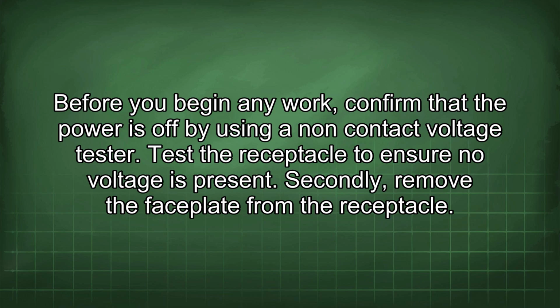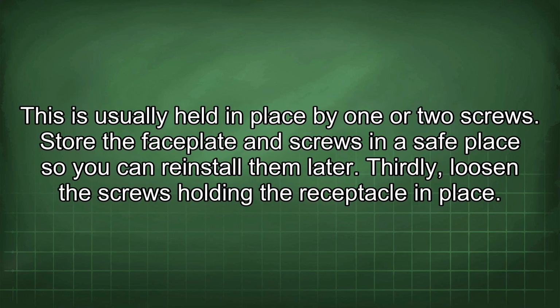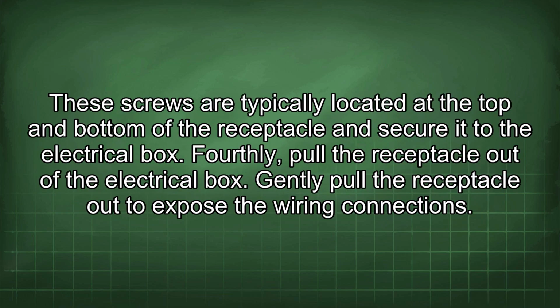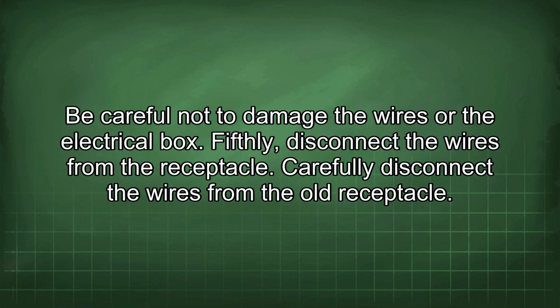Secondly, remove the faceplate from the receptacle. This is usually held in place by 1 or 2 screws. Store the faceplate and screws in a safe place so you can reinstall them later. Thirdly, loosen the screws holding the receptacle in place. These screws are typically located at the top and bottom of the receptacle and secure it to the electrical box. Fourthly, pull the receptacle out of the electrical box. Gently pull the receptacle out to expose the wiring connection. Be careful not to damage the wires or the electrical box.